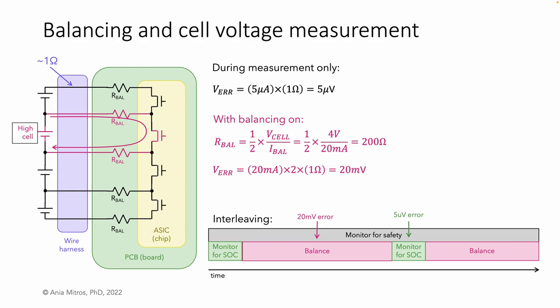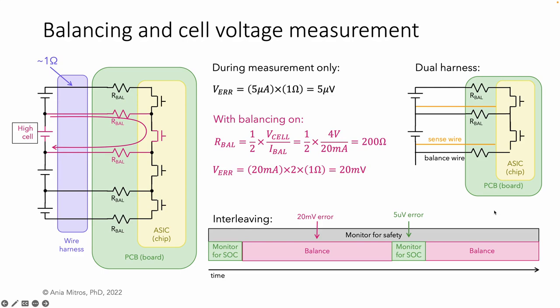state of charge estimation. As we will learn later, better accuracy is desired for state of charge estimation than for safety. An error of 10 or 20 or 30 millivolts may be tolerable within the safety architecture and problematic for state of charge estimation. Another option is a duplicate harness with 2 wires to each cell, one for balancing and the second for sensing. Cost is a concern for the dual harness solution.